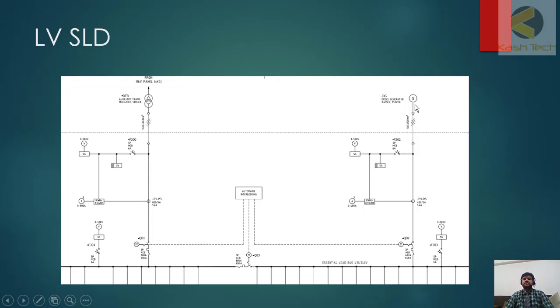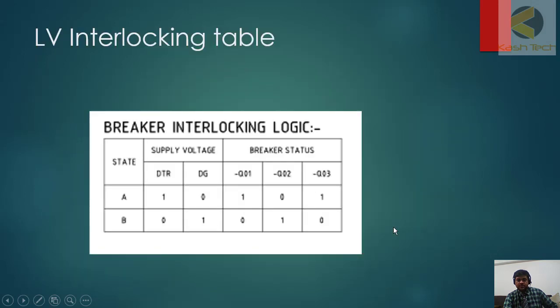In the second case, if the supply from the transformer is failed, incomer one will become open automatically. After two or three minutes, the generator will be feeding supply. The coupler will remain open and the generator will be feeding supply which is connected only on the essential bus.